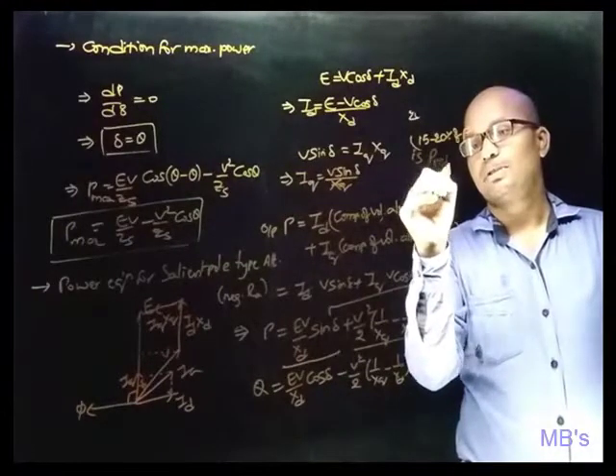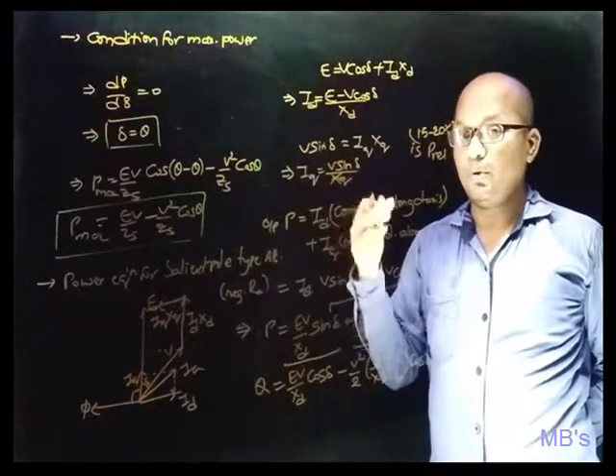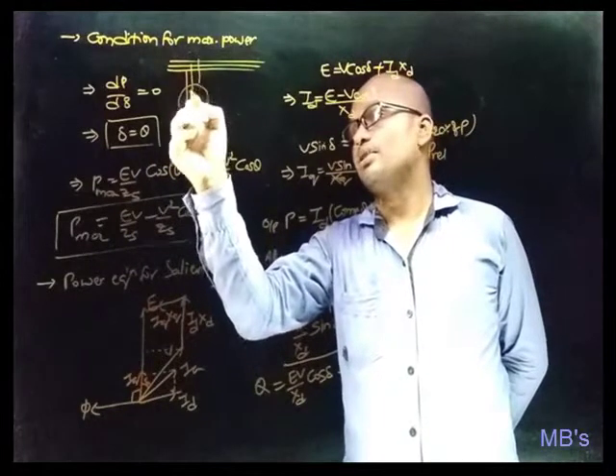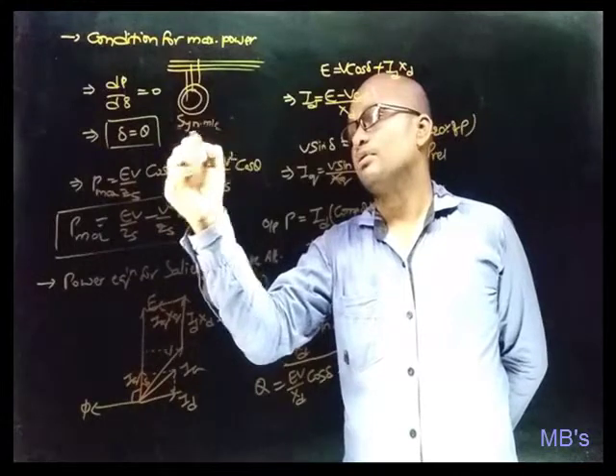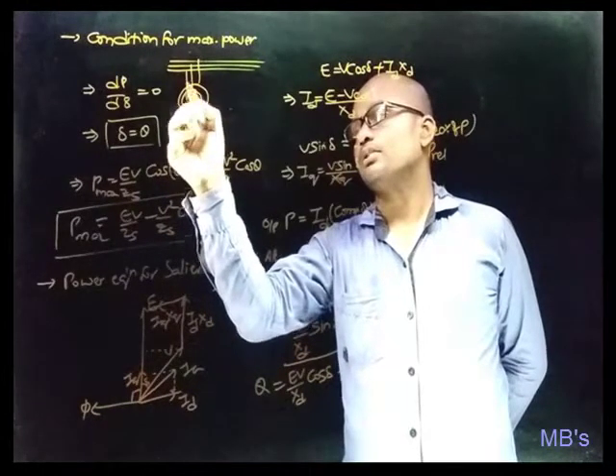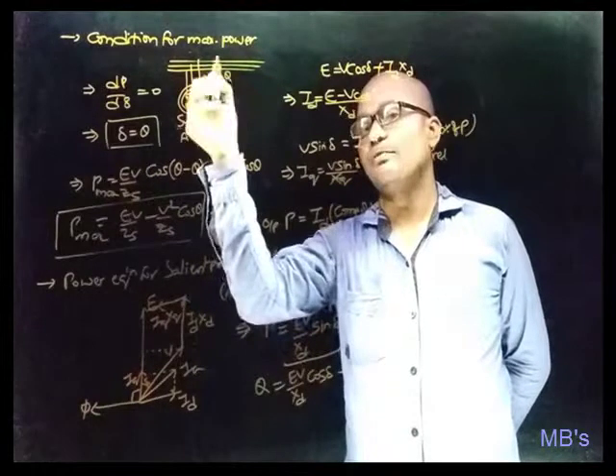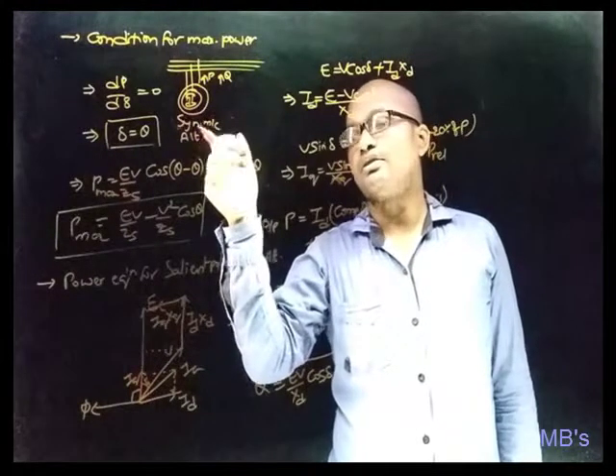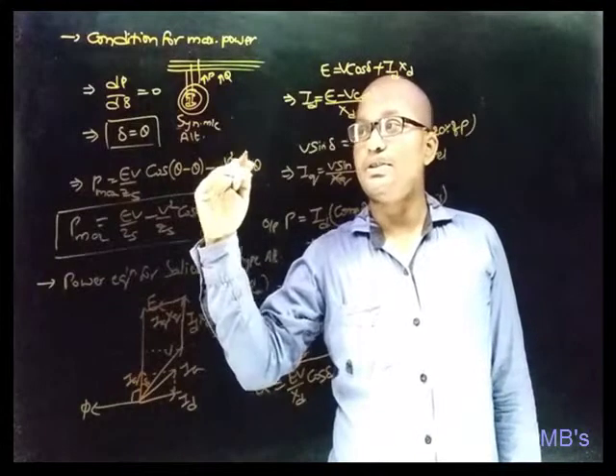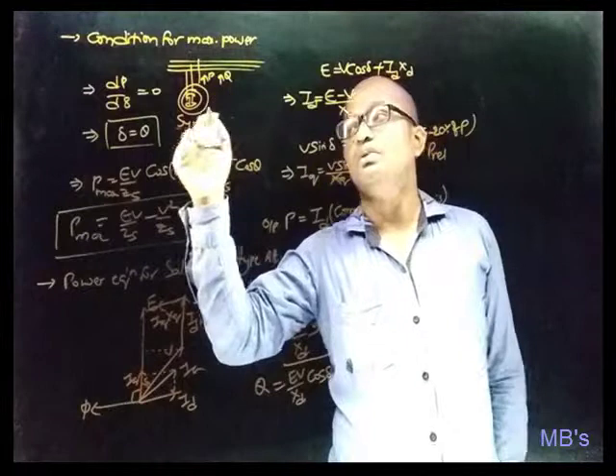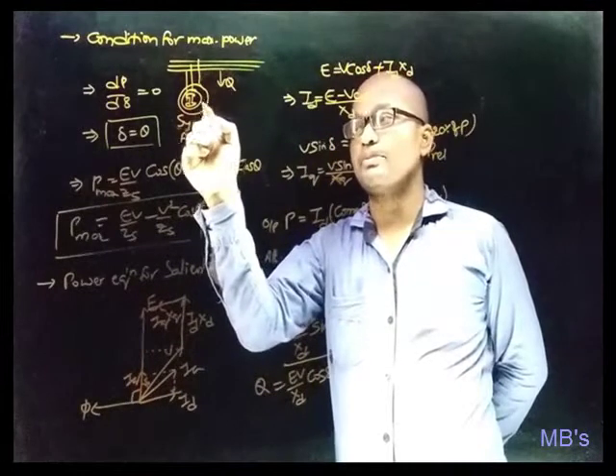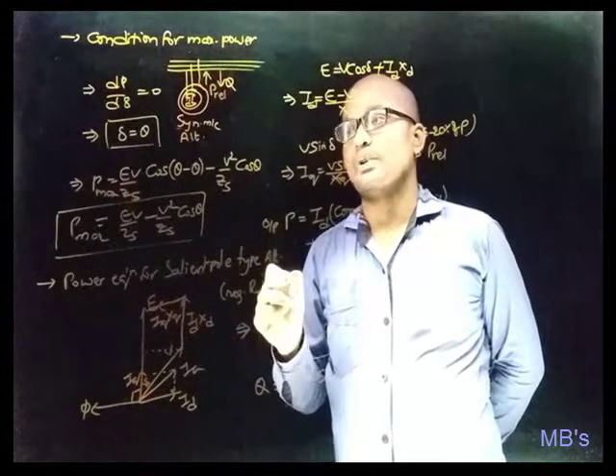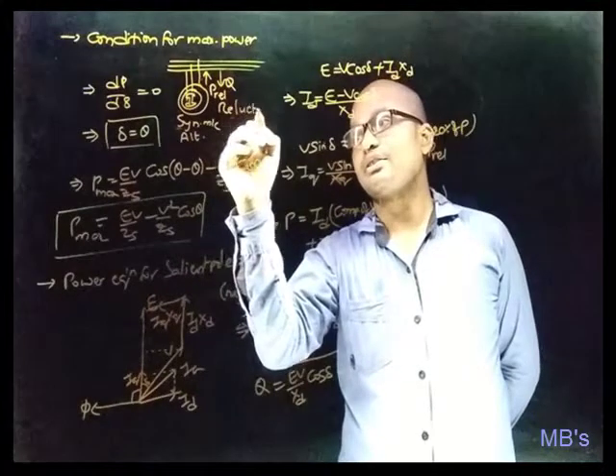The reluctance power constitutes about 15 to 20 percent of the total power. When a salient pole alternator is connected to an infinite bus bar and field excitation fails, it continues to deliver power. It takes reactive power from the bus bar to create working flux and then delivers reluctance power, acting as a reluctance generator.